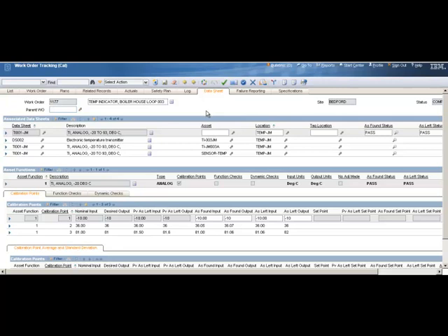It told me what the status was of each point and the overall datasheet. I completed out the work order. So that calibration is complete. Again, loop calibration is a cluster of instruments all calibrated together as one unit. And if they all work together right and the loop calibrates, no further need is required to calibrate the individual components. If any one fails, then you can calibrate the individual components and find which one is bad. This pretty much concludes our presentation on the calibration functionality within Maximo version 7.